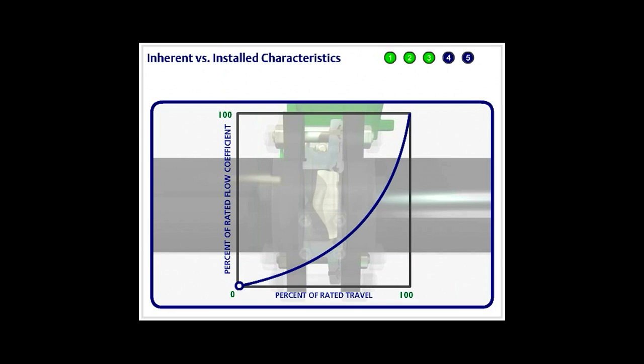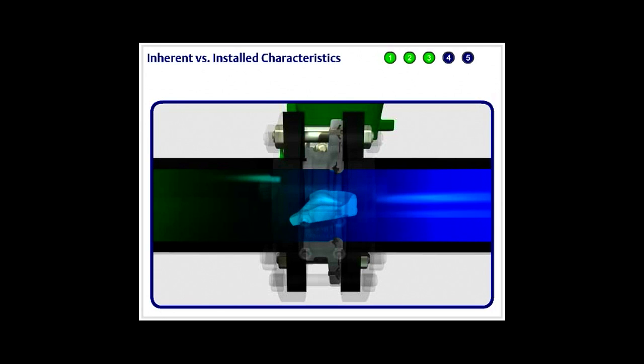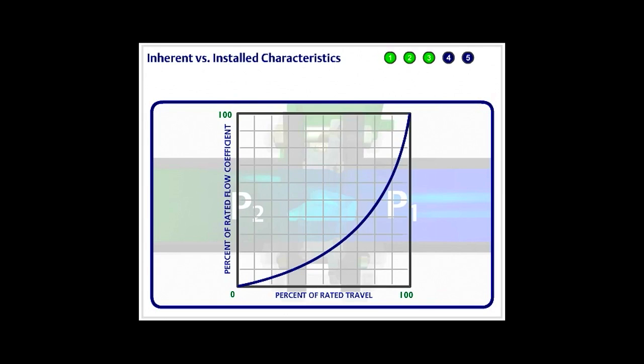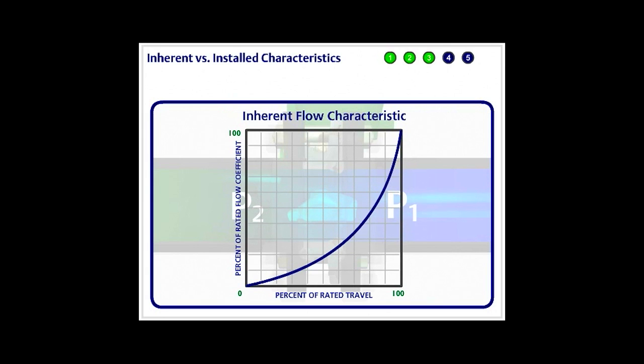Note the lower flow rate, which affords better control at low to mid-valve open positions, with a rapid change in flow rate as the valve approaches full open. The inherent flow characteristic is determined by a standard flow test, in which the only variable is a change in valve travel, going from fully closed to fully open.